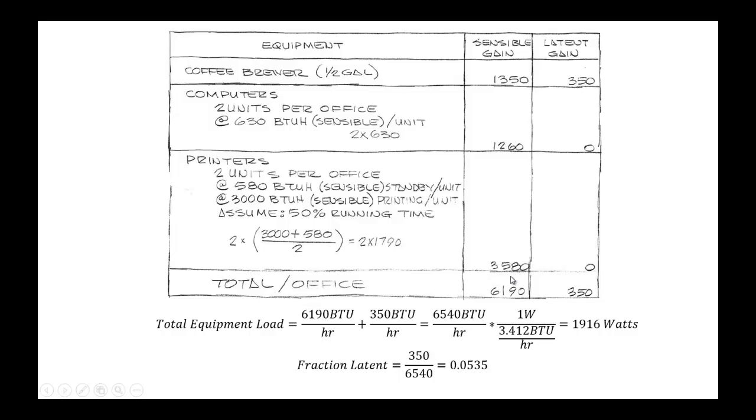So once you add these two together, you get a total equipment load of 6,540 BTUs per hour. However, Energy Plus and OpenStudio like it in watts, so we convert to watts by using this unit conversion formula, and there's the total watts of heating load from the equipment.